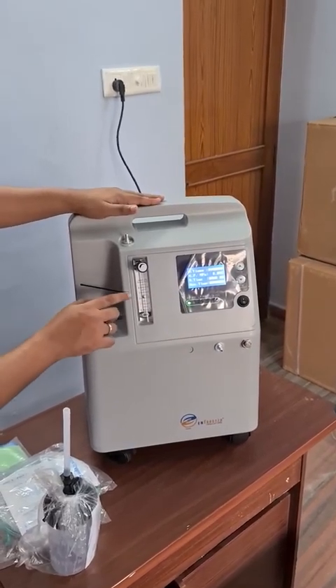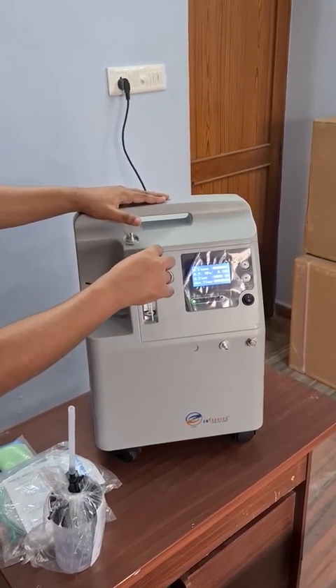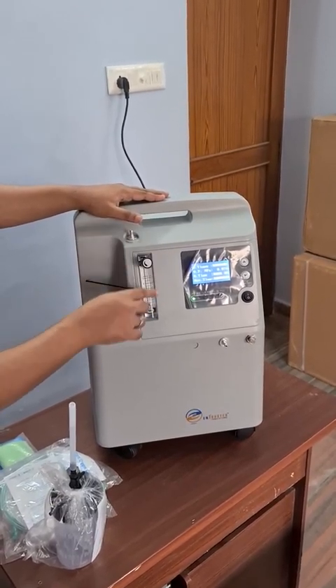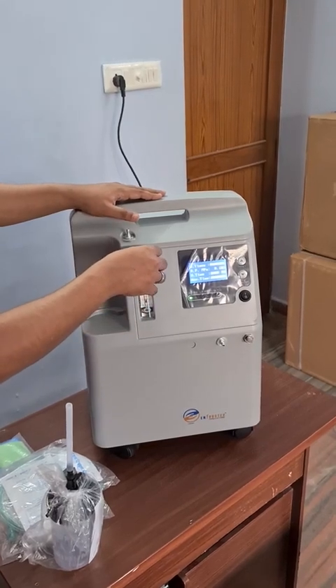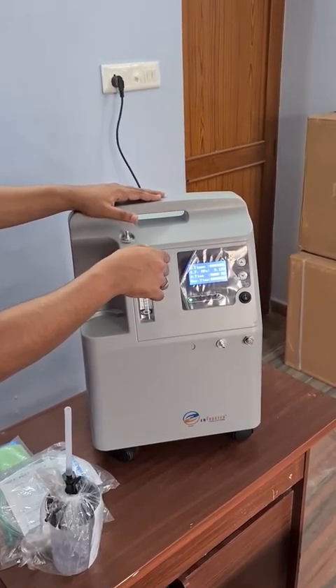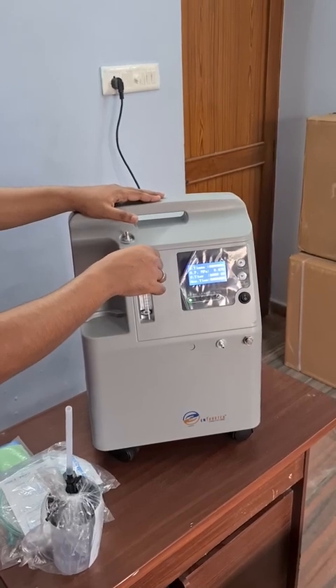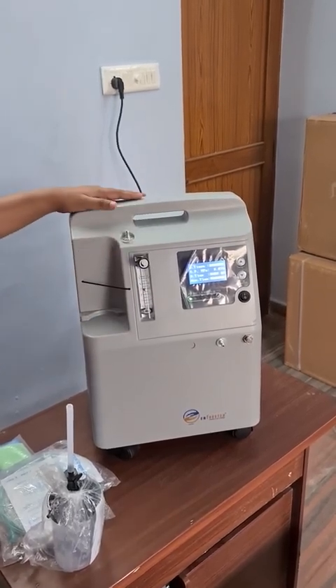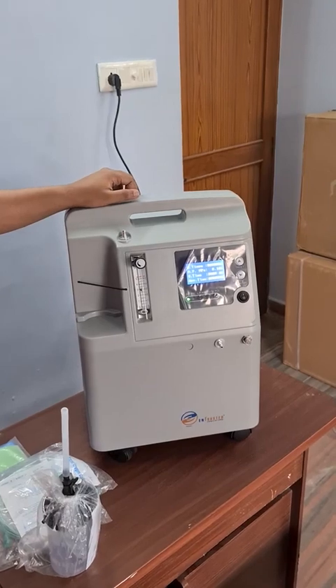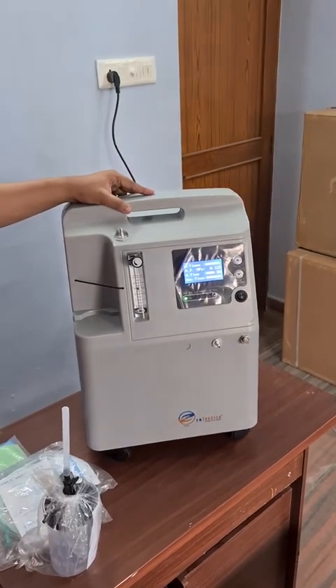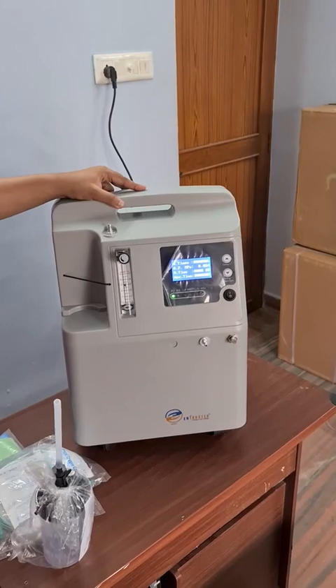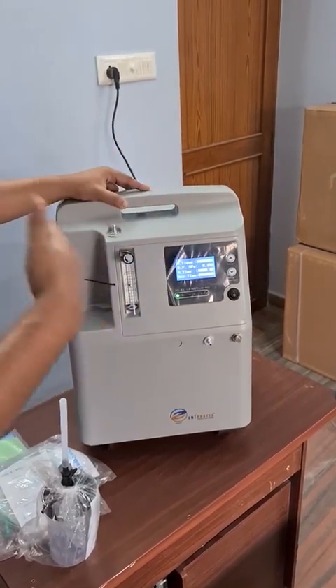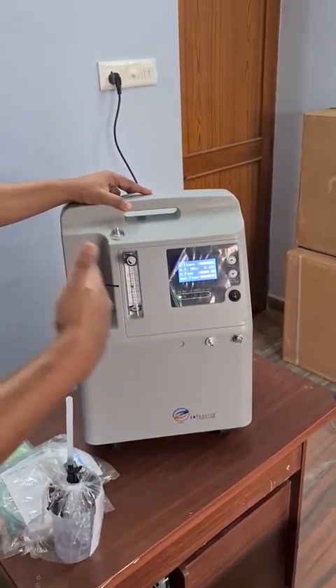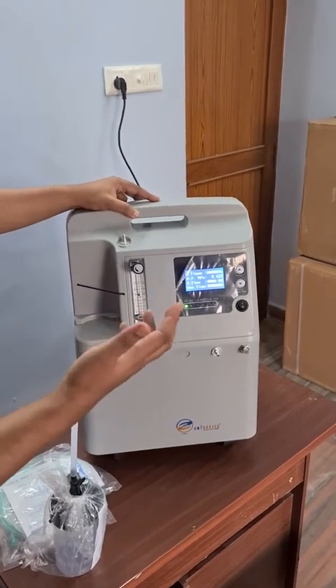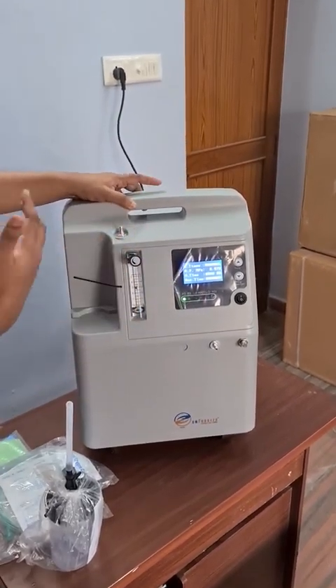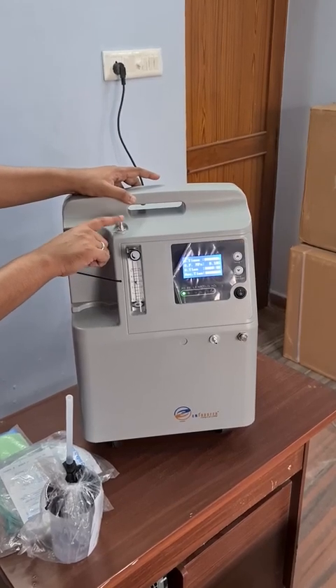The machine is running fine, and you can see, if I rotate this knob clockwise, it decreases the oxygen flow rate. When I rotate anti-clockwise, it increases the oxygen flow rate. If you observe carefully, every 8 seconds you will hear a flush sound. That sound is the nitrogen getting exited from the device. When nitrogen exits, the machine stores oxygen and delivers purified oxygen from this output port.